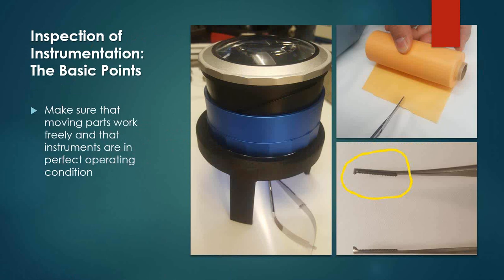On the top right, I also want to add that testing your scissors and instrumentation in general with all the testing recommended by the IFU of the instrument vendor is very important. A scissor here may cut clear and clean, but you want to make sure it doesn't snag - if it does snag, it's going dull. One thing to keep in mind is that a scissor can cut clean but still make a noise or cut roughly. Make sure you take it out for repair because there could actually be something lodged in the box locks in that area, or there could be some damage.